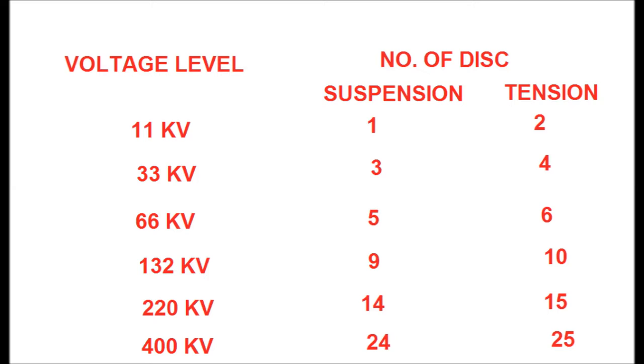In summary, the number of discs and voltage levels are shown in the figure. For 11 kV: suspension string uses 1 disc, tension uses 2. For 33 kV: suspension uses 3, tension uses 4. For 66 kV: suspension uses 5, tension uses 6. For 132 kV: suspension uses 9, tension uses 10. For 220 kV: suspension uses 14, tension uses 15.